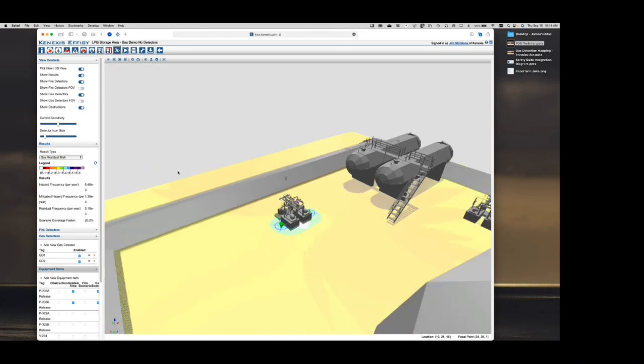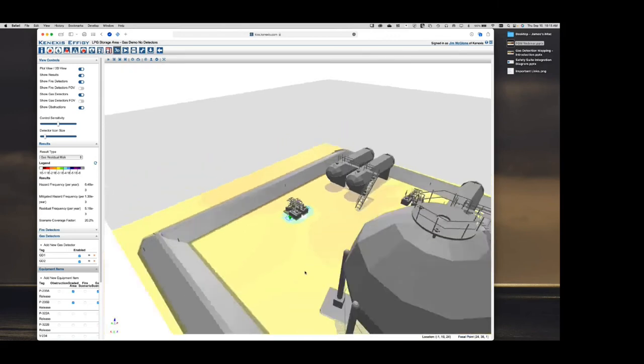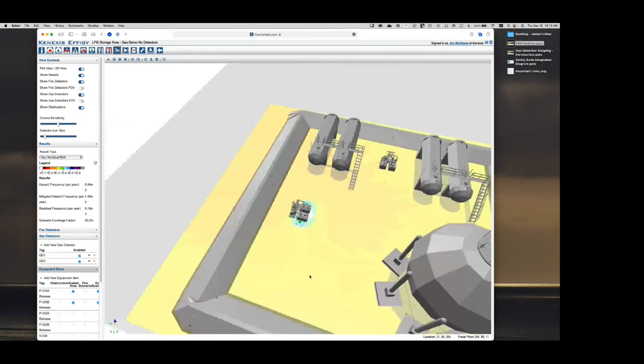Wow, that doesn't look right at all. Things look really strange here. I see all this yellow area, which is like 5 times 10 to the minus fourth to 1 times 10 to the minus third, and some orangish area, which is starting to approach 5 times 10 to the minus third. I can see the cloud shapes here. What's different is we're not doing geographic anymore. We've moved to scenario. The geographic coverage was in essence 100% covered, but scenario coverage is only 20.2% of the gas clouds covered. So the gas is almost never actually in this graded area.